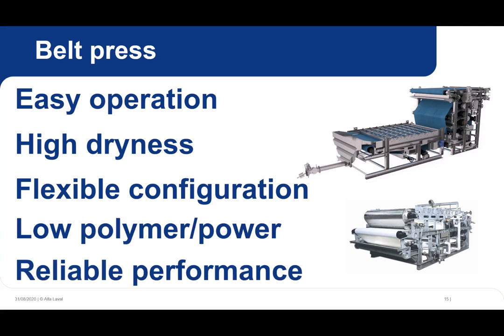The belt press dewatering process begins when flocculated sludge enters a distribution box and is spread over the width of a gravity deck that consists of a continuous porous belt. As the product moves down the belt, plows, also called chicanes, repeatedly split the flow and start the process of releasing water from the product. The porous belt allows water to escape and drain into a collection pan below.